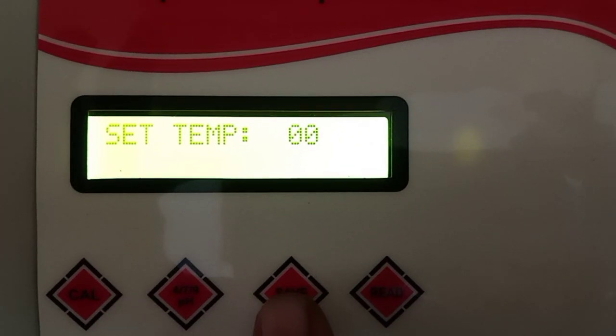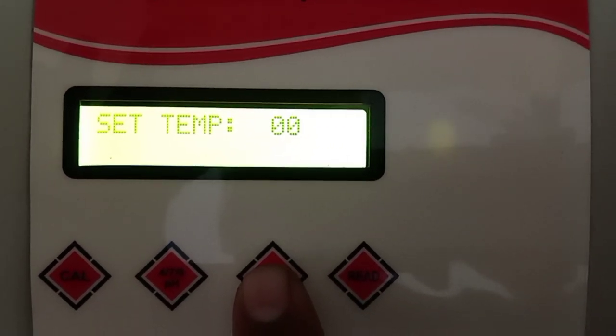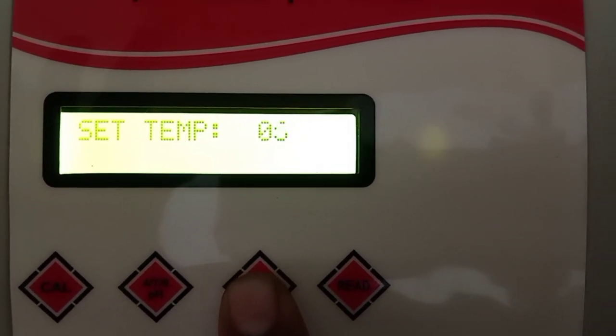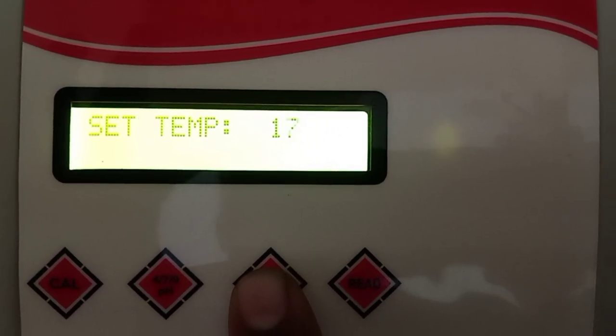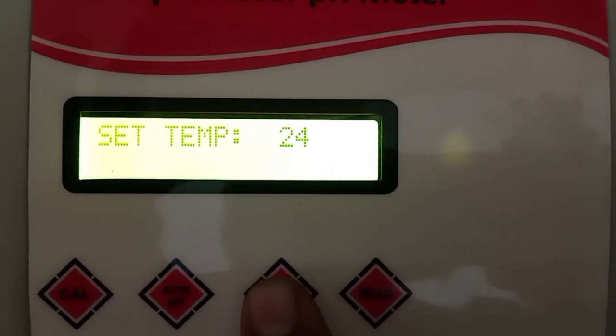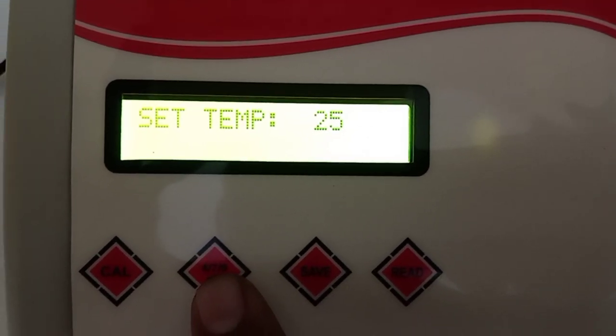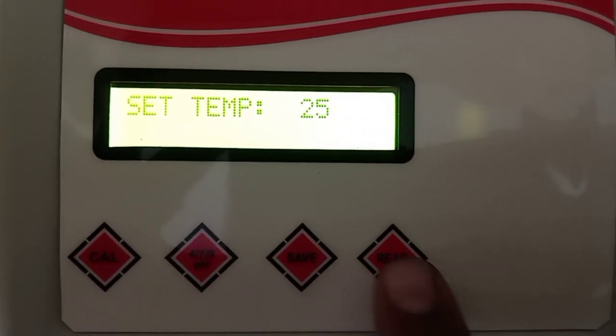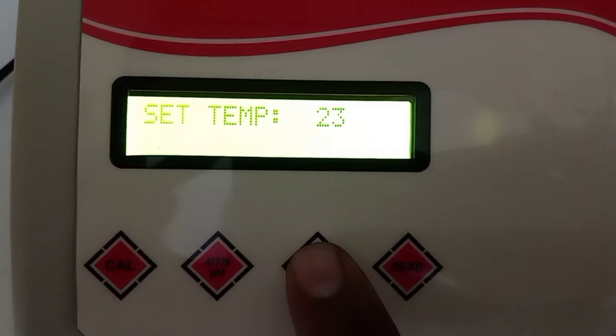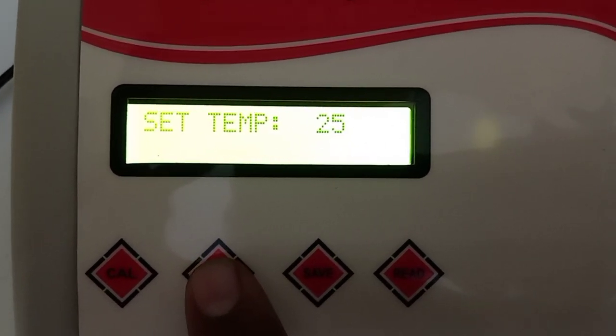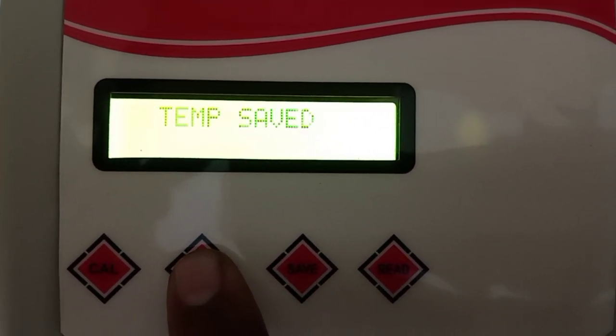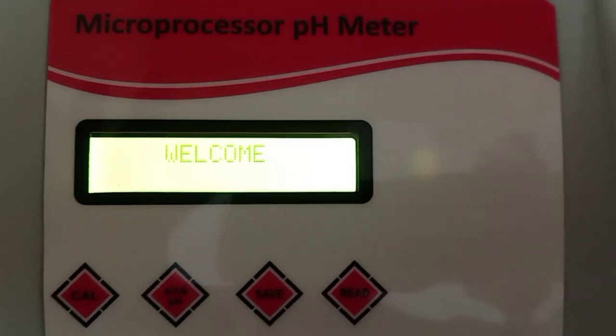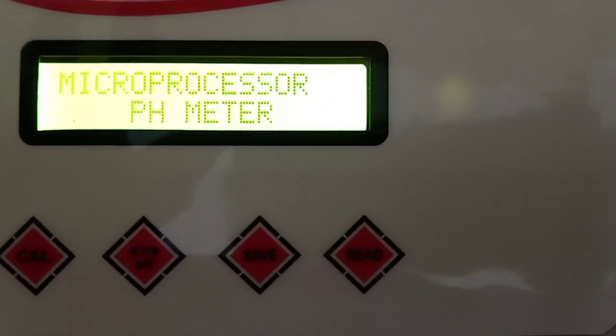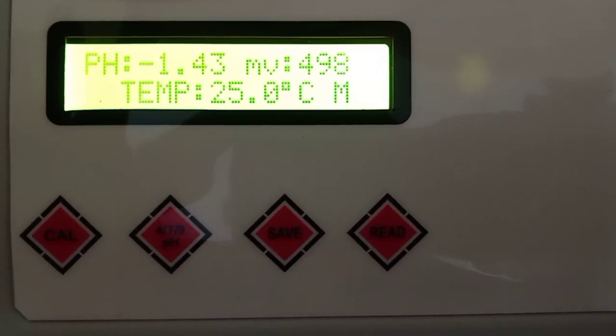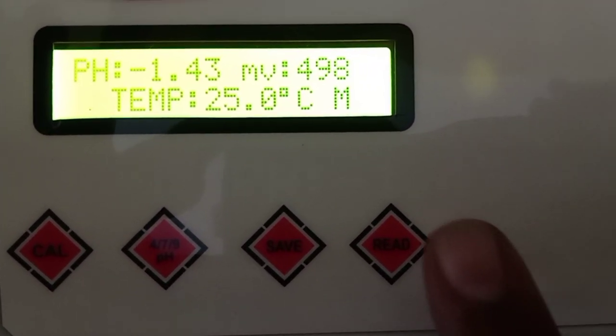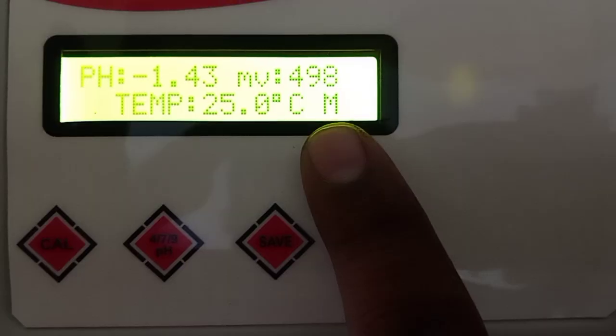Press cal. In calibration mode, we have to set the temperature. Like you want to set 25 degree. And read button is used to decrease the value. So we are setting at 25 degree and press second button to save the value. Now in the home screen it shows M 25 degree, that stands for manual temperature compensation.